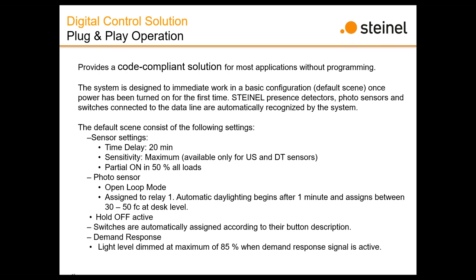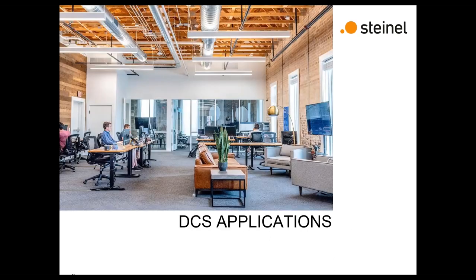So whenever you look at the different room types, simply by selecting the proper switch, then you can have a new plug-and-play sequence of operation. And then beyond that, yes, you can use the use cases. But the simple plug-and-play, we tried to make it so that it's code compliant for all of these things. Demand response is also code compliant out of the box for the state of California. So when it receives the demand response signal, it's set at a maximum 85% of design illuminance for that space. That's the base. There's other pieces, but those are the most important.